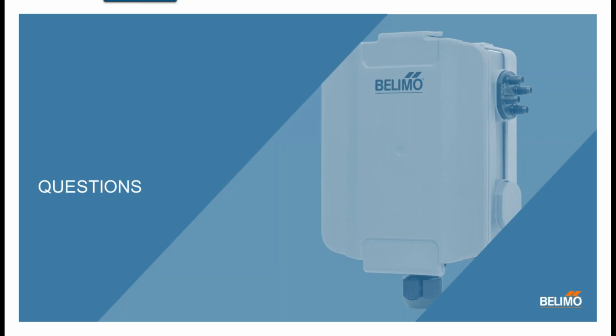Okay, the safety sensors like freeze stat and pressure switch, do they have single pole or double pole relays? The pressure switch, well, they both have single pole double throw. And for the freeze stat, the low temperature detection, for first phase it will only be single pole double throw. We do understand that a double pole double throw will be needed, and that will be coming in the next phase as soon as possible.